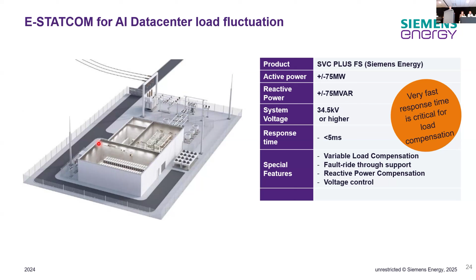Last time I presented this was actually at ESIG 6 months ago, and most of the questions were about the control philosophy we use, so I added a slide to clarify this a little bit. The E-STATCOM as a product comes with two different control philosophies. One is grid forming, which is typically used by utilities to provide inertia services like a virtual synchronous machine. When we try to apply the grid forming approach to this problem, we quickly realize that it does help, but it might not be the most efficient way to deal with the load fluctuation.